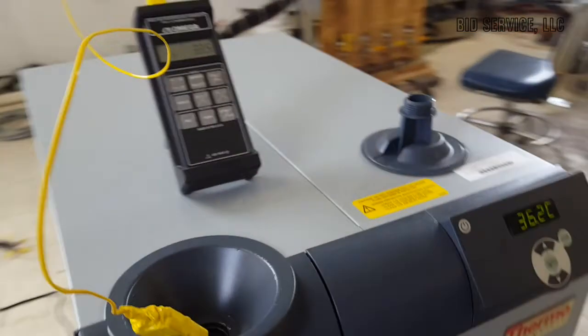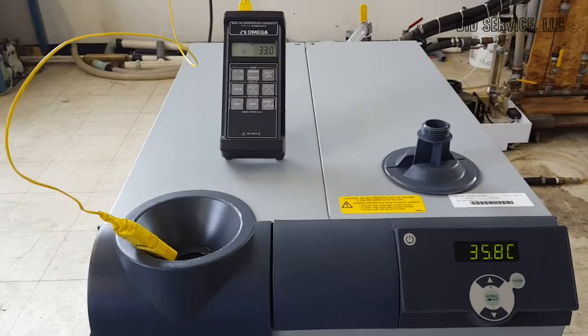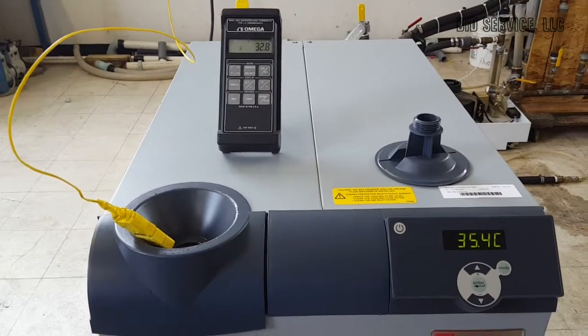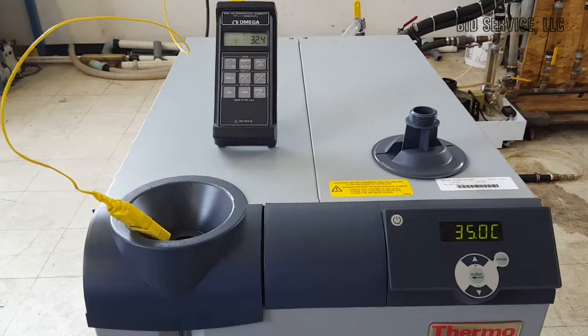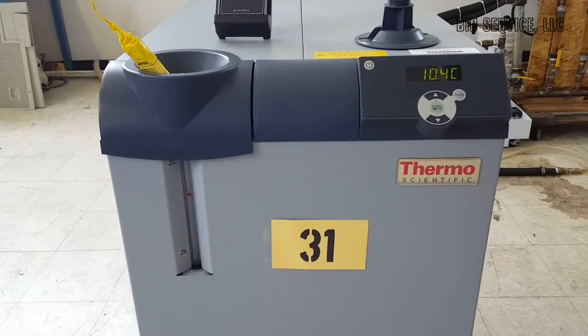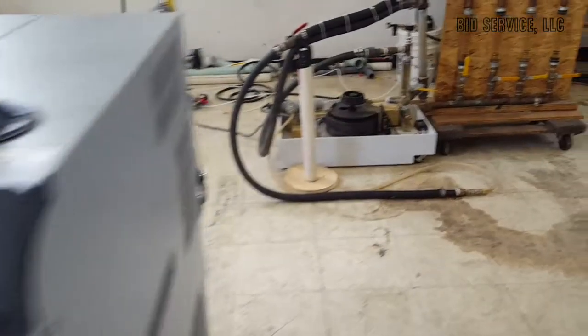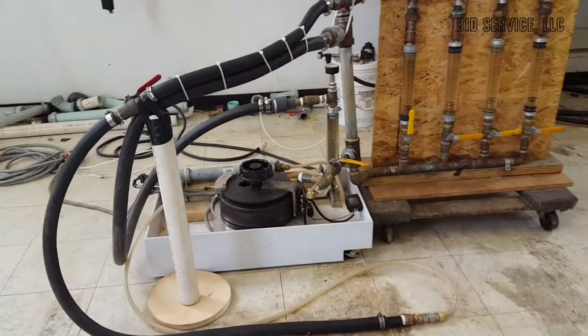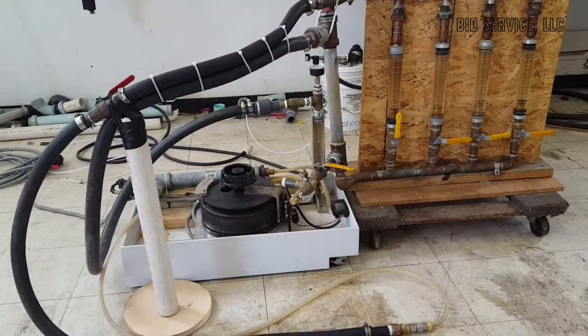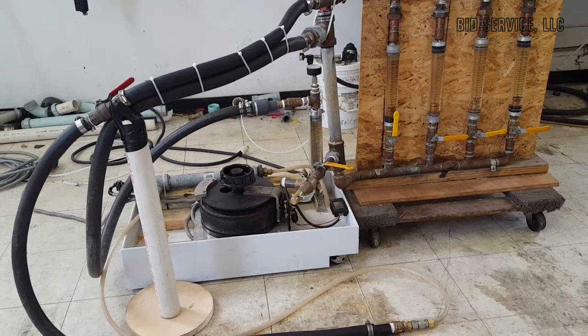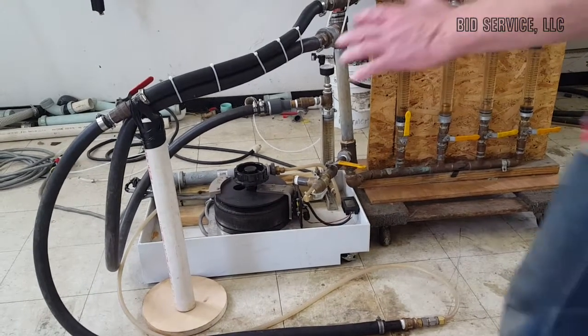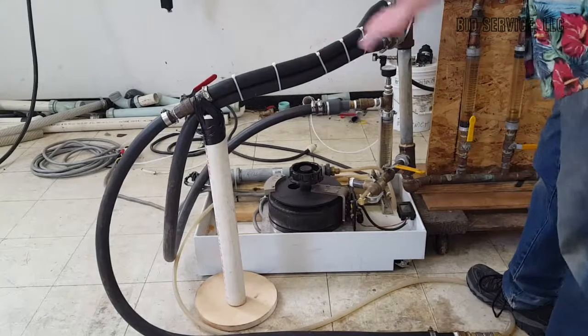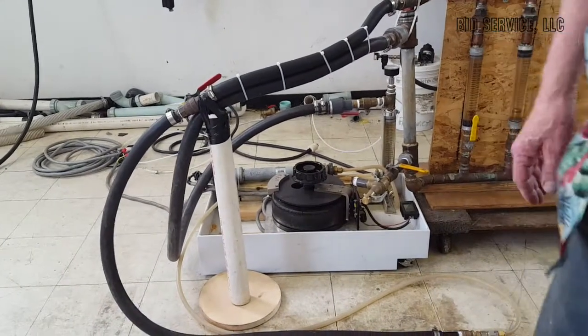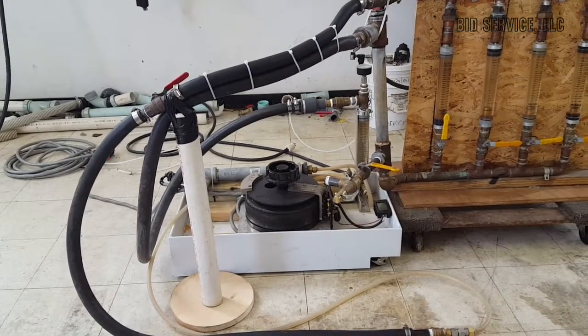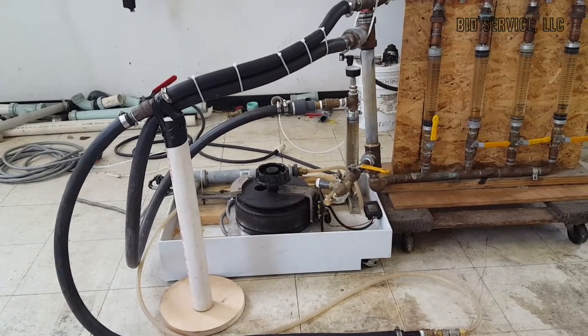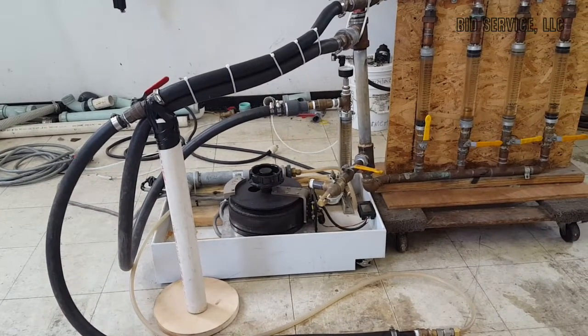Oh, as you can see, we're already on our way down. So we'll just come back in a few minutes and see how we're doing. Almost all the way down, but while we're waiting, we also test the system for load. It's rated 3,500 watts at 20 degrees C. Actually, we hook up 2 of these setups together, and I tested this system for 2.5 hours at 3,800 watts at 20 C, and it had no problem whatsoever holding that temperature.